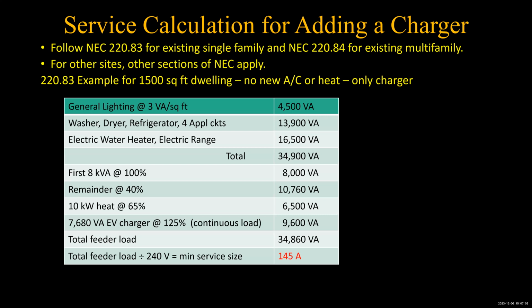And then you throw in your 10 kW of heat at 65%, at 6,500. And then the next thing you add is your 7,680 volt amp EV charger at 125%. That's 9,600 volt amps. And see, we're just adding that right in with the 10 kW heat at 65%. We're doing the charger at 125%. And this is after we've done everything else in at the 100% for the first 8 kVA and the remainder at 40%. And that's all the stuff up here, the refrigerator, appliance circuits, water heater, range, computer, pool pump, whatever it is. You do your calculation and see what you got.